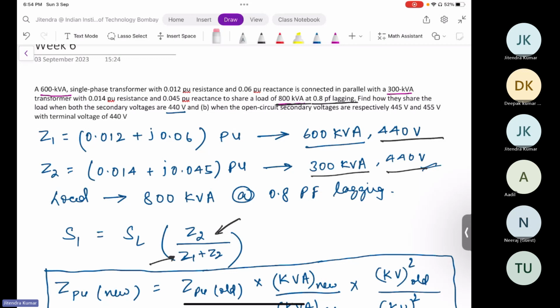Because kVA rating is not a scalar quantity, it is a phasor quantity, so you have to check at what power factor it is operating. Both things should be satisfied, because power rating and power factor here signify how much real power and reactive power demand is occurring at the load side. According to that, your transformer will supply.